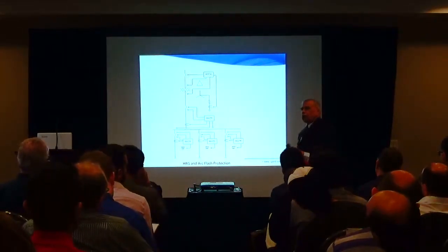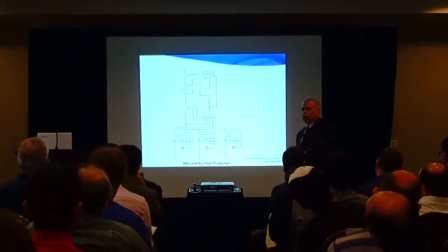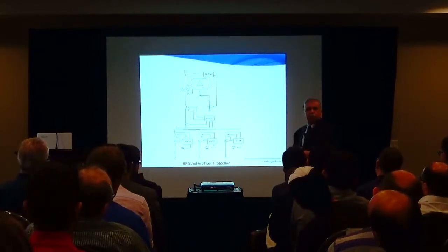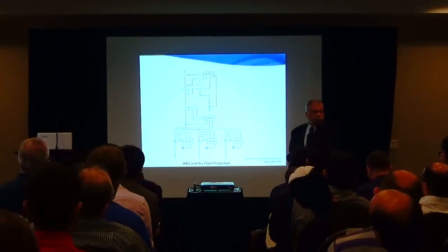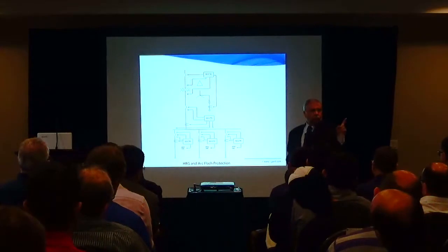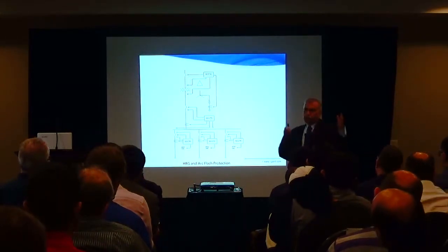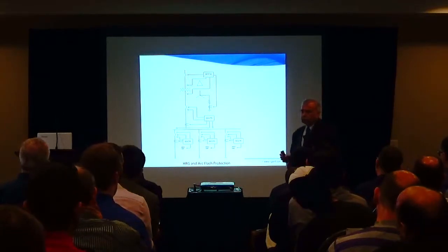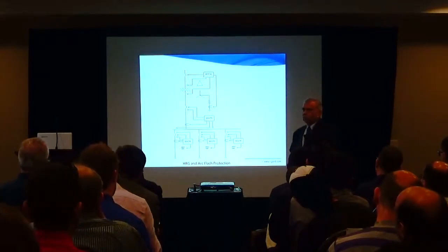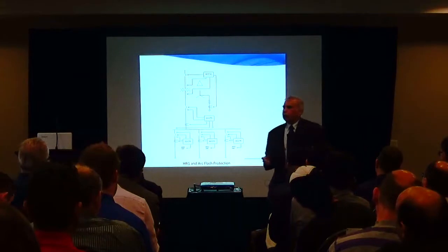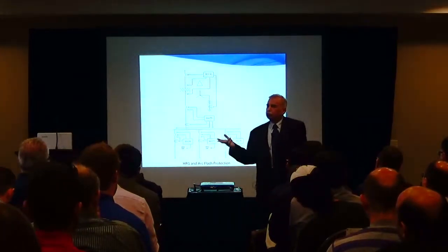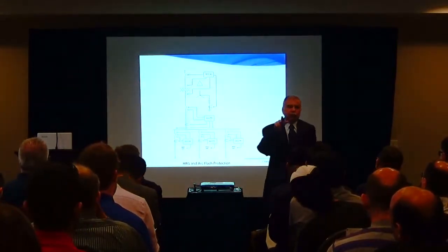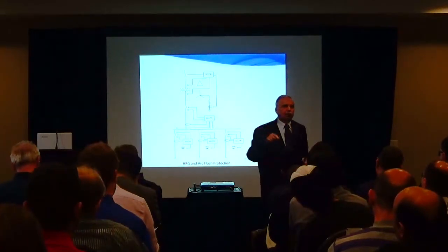So we said, have you thought of arc flash protection? Have you thought of optical sensing relays? All they had to do was to replace the load break in the same enclosure with a vacuum interrupter. And that's it. So that's an incremental cost. It's not a full scale replacement. Just the load break needs to be replaced with a vacuum interrupter.